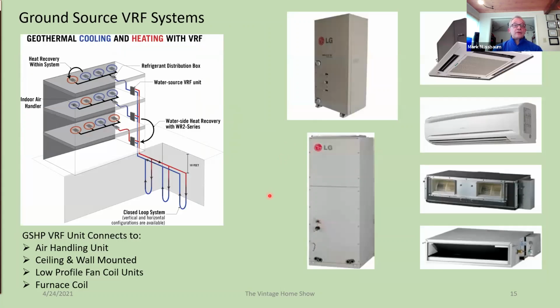The VRF system, variable refrigerant flow system, sometimes called variable refrigerant volume systems, depending on the manufacturer. The difference between this and the slide before is that this box, again, sits inside, and then it can connect to multiple boxes inside. So I can have one box connected to the ground loop, and I can share that capacity with other air handling units, fan coil units, ducted fan coil units, unducted or ductless units that might sit there or be recessed into a ceiling. Some manufacturers have a furnace coil that it can connect to, so you can blend it in with an existing system.